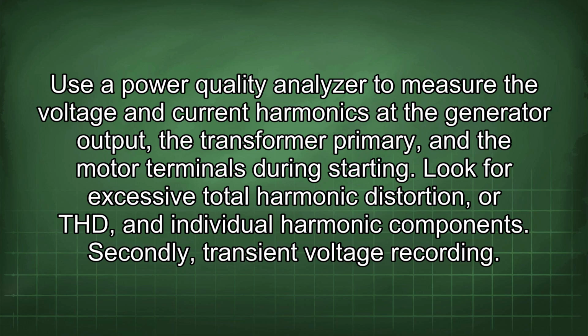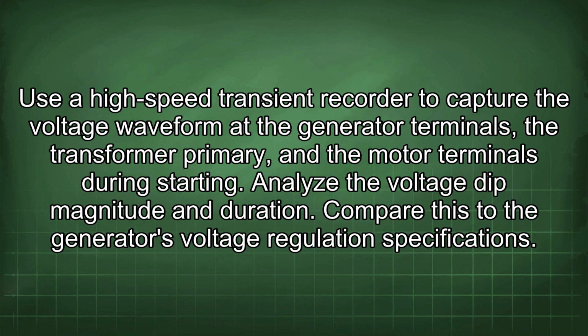Secondly, transient voltage recording. Use a high-speed transient recorder to capture the voltage waveform at the generator terminals, the transformer primary, and the motor terminals during starting. Analyze the voltage dip magnitude and duration.